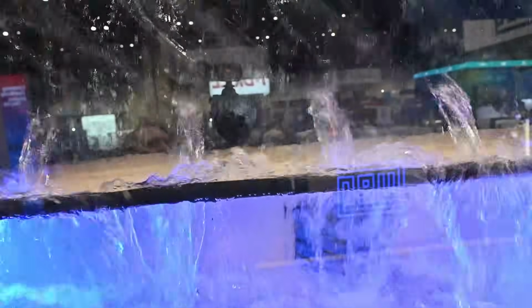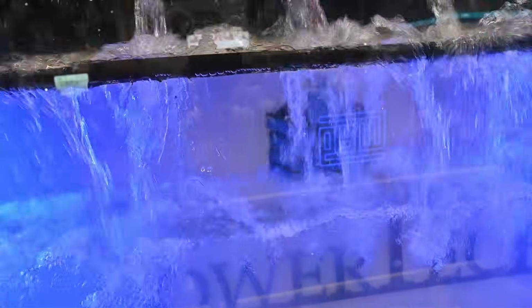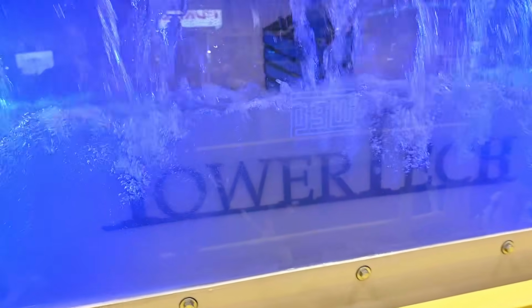With the bottom-mounted fan design, you have a flow-through basin, so water flows through the tower at high velocity. It keeps the solids in suspension, so the chemical treatment requirements on our tower are much less because we're keeping the water moving. You can often run our tower at higher cycles, you don't have to use much chemicals, and if you can do that, you potentially save water on bleed or blow down.